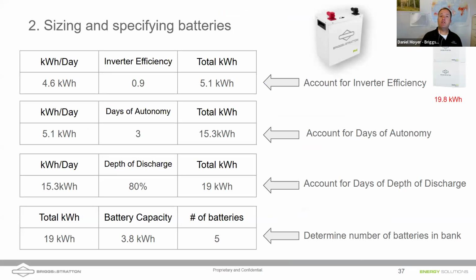What we know is all batteries aren't 100% efficient, right? 0.9, actually ours are probably a little more efficient than that. Most lithium ion batteries are, but we're going to lose 10%. Well, I'm sorry, the inverters, right? Inverters aren't 100% efficient, we're going to lose about 10%. So we know that we need to bump it up. Now we need 5.1 kilowatt hours per day.